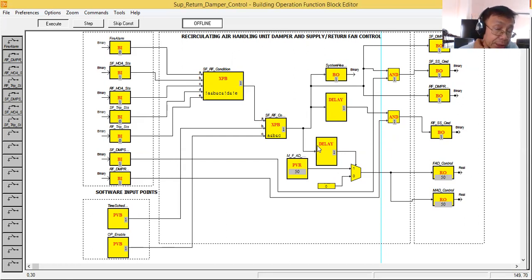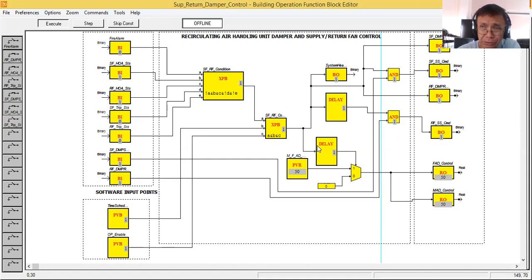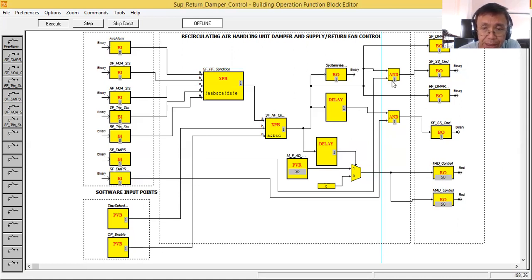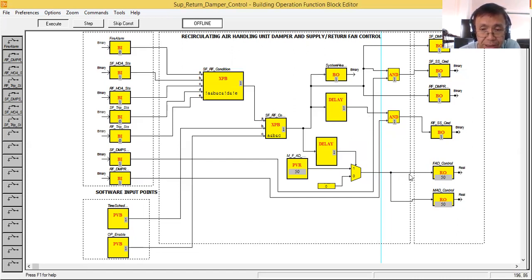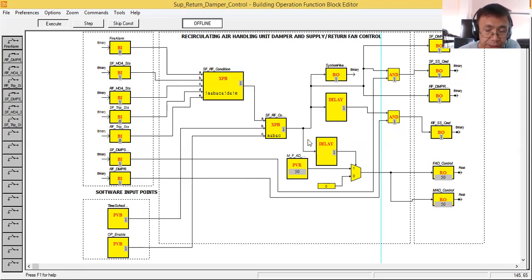This is the typical simple control for dampers and the air handling unit. For new BMS engineers, make sure the dampers are open first before starting the fans, because it is very dangerous — it might burst the supply ducting if the fan starts while the dampers in the supply duct are still closed.